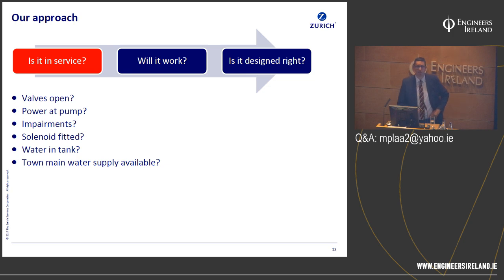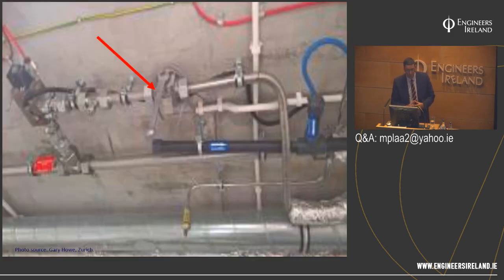So, is it in service? Well, that's quite simple really, by having boots on the ground, checking the valves are open. Every year when I do site assessments, I'll find valves closed. Pump switched off, is the power? Impaired systems. On water mist systems, I will find solenoids disconnected from high pressure cylinder banks, just hanging in midair. Water in the tank, I'll physically get up there and check we've got water in the tank. And if it's the town's main system, have we tested the supply to make sure we're getting the adequate pressures and flows? Here's one example of a water mist system that I went to see in a high-rise building.